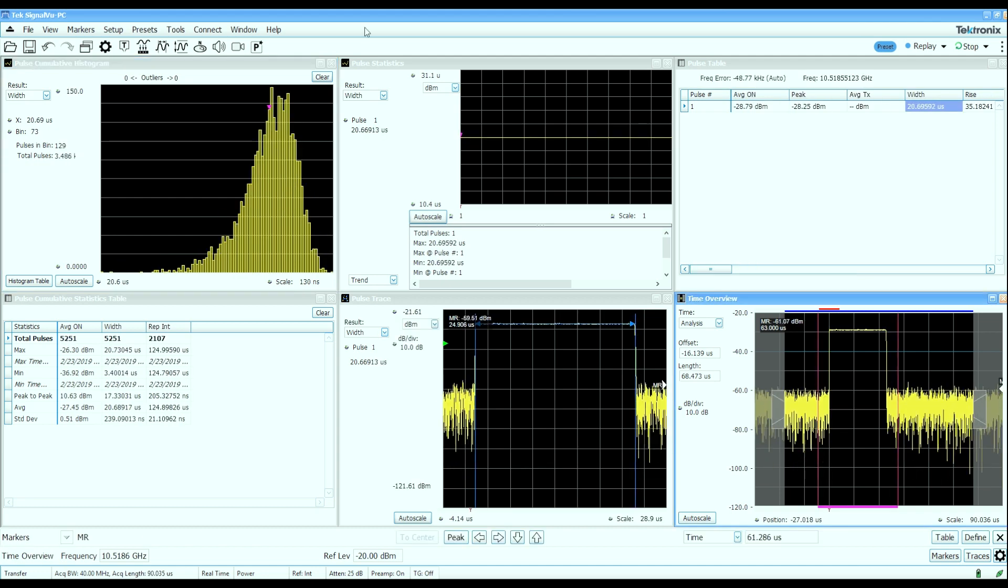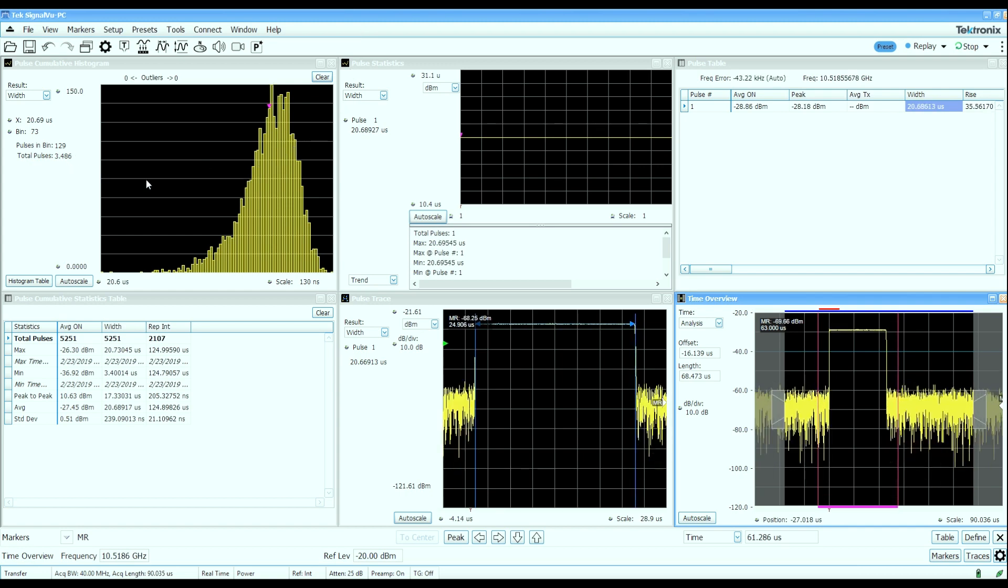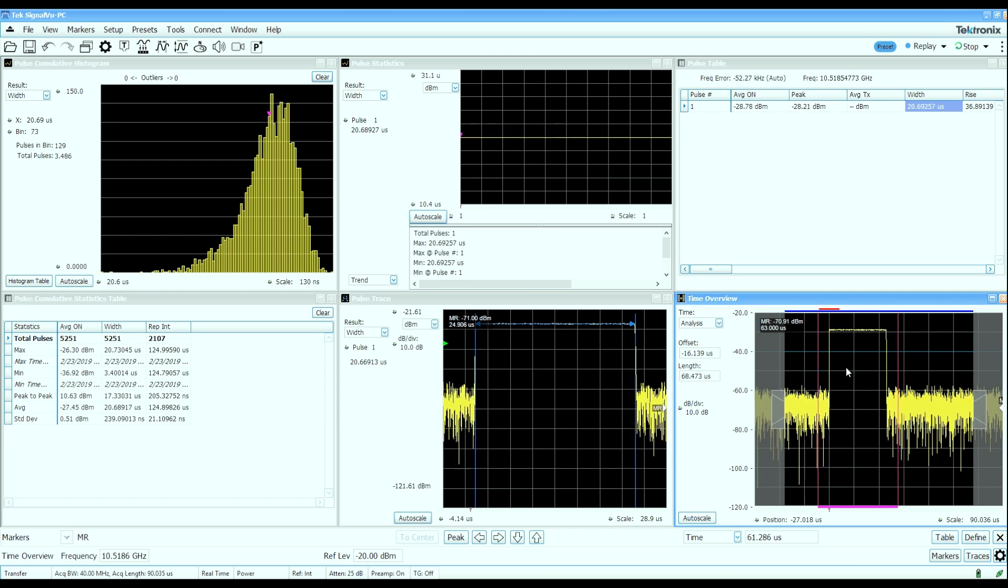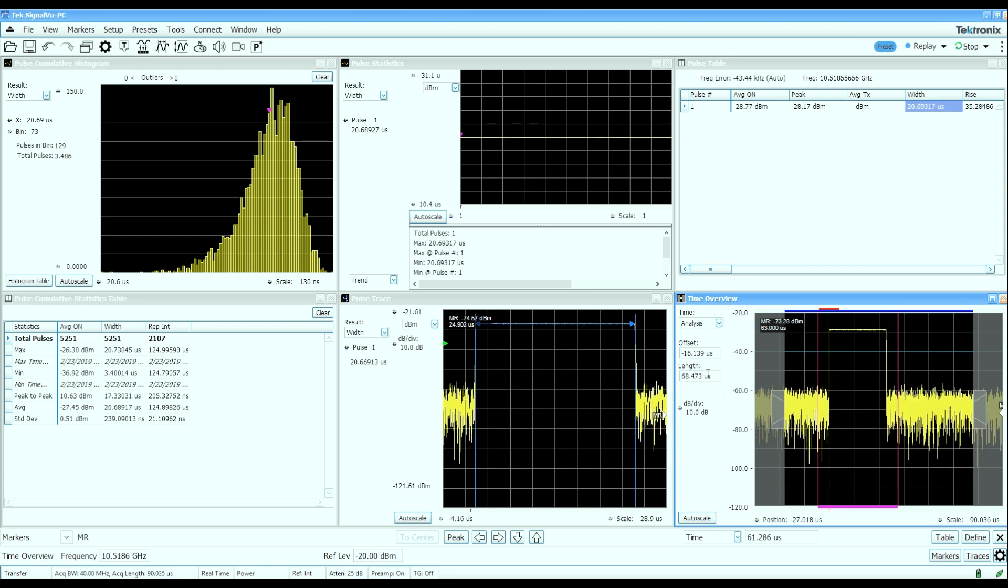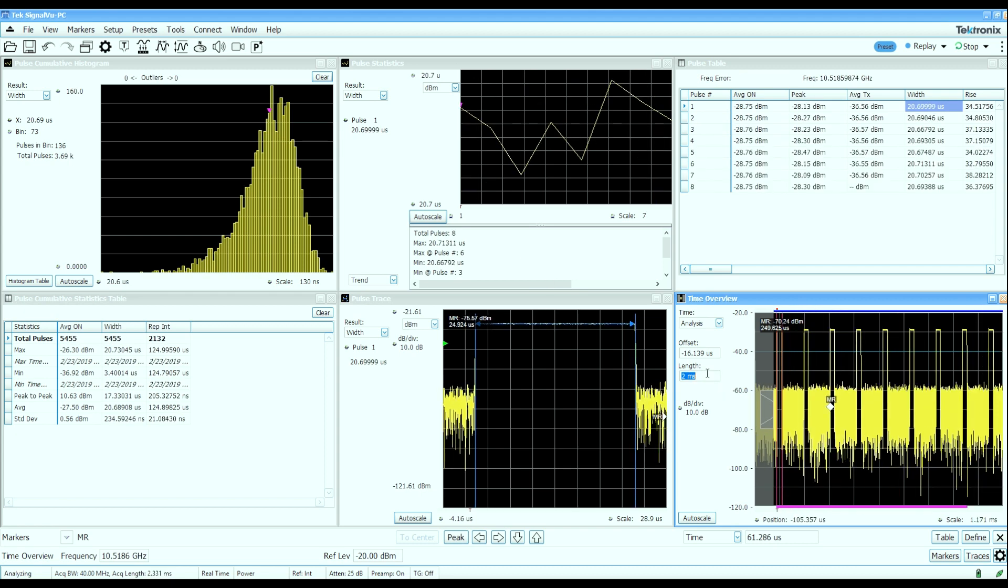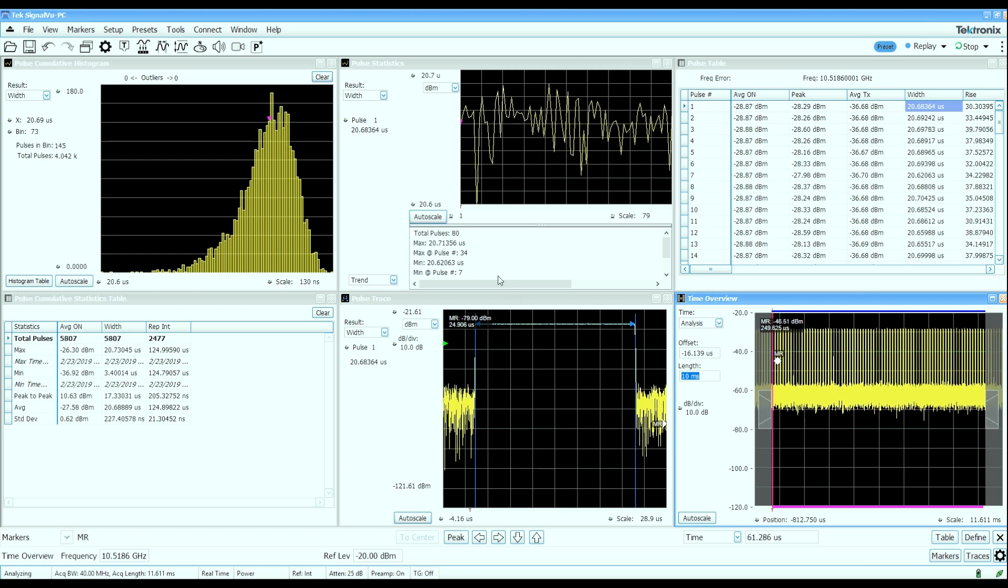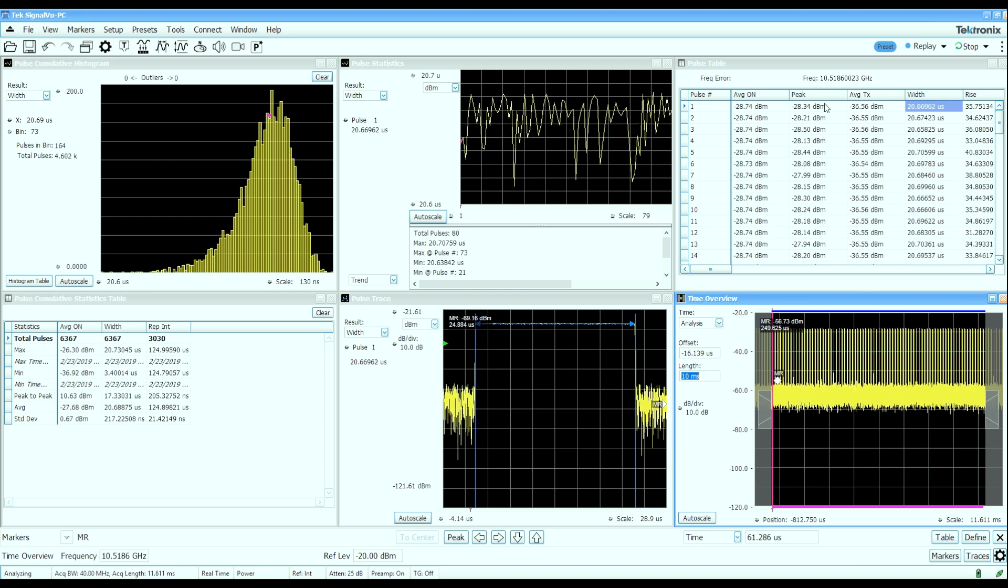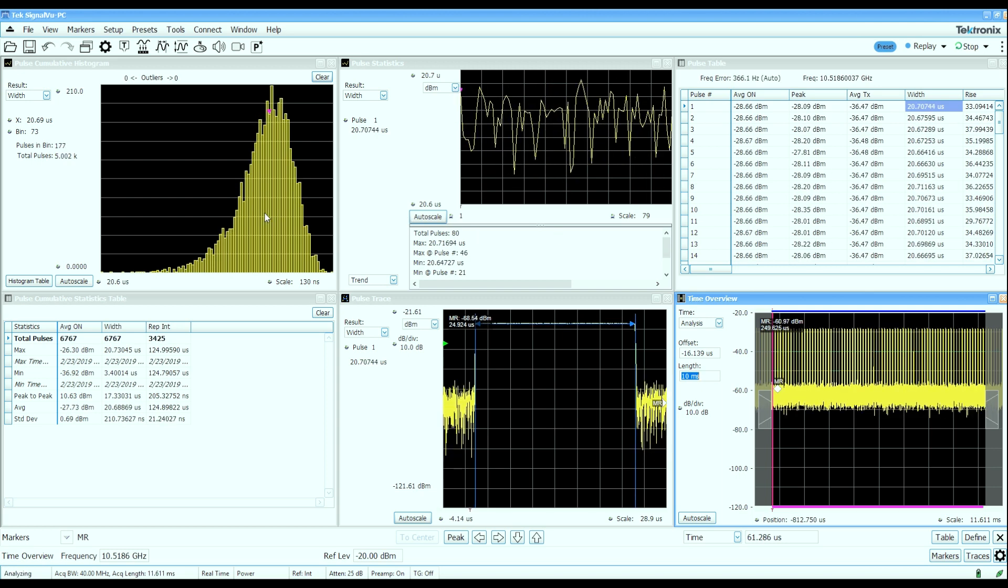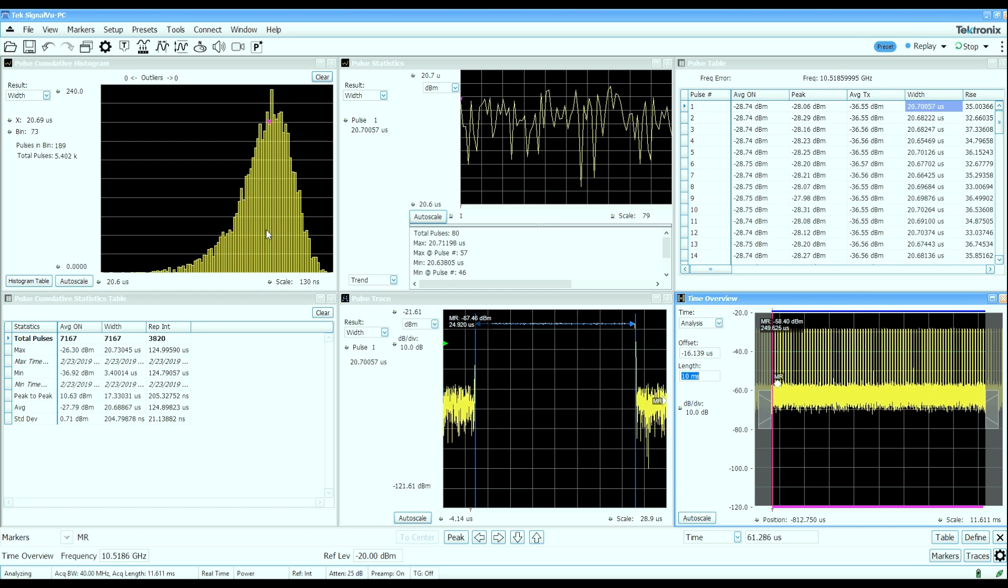I've let the cumulative statistics build up here for almost 3,500 pulses that we've captured. But this is doing it one pulse at a time. The cumulative statistics as well as the instantaneous statistics will work with long acquisitions as well. So if I collect a much longer set of acquisitions here, now essentially I've got my pulse statistics plot will show me the characteristics for a seamless acquisition while the cumulative statistics continue to build results from all the prior acquisitions.